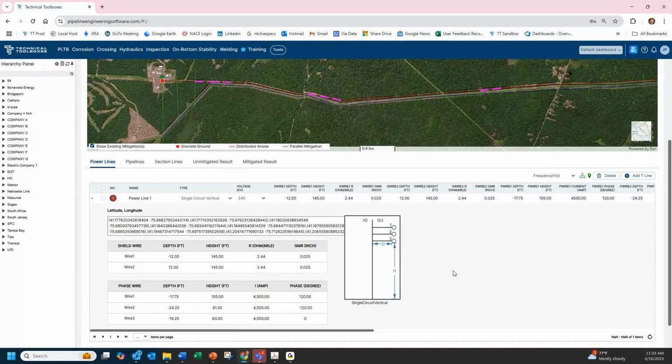It's more field related, and also if you have coupons out there, if you're doing any kind of AC studies, when you do a study, make sure to use data loggers to see what's really going on, not just during the day, but what's going on at night. That was the biggest surprise I ever saw, that issue I showed you in New Jersey.